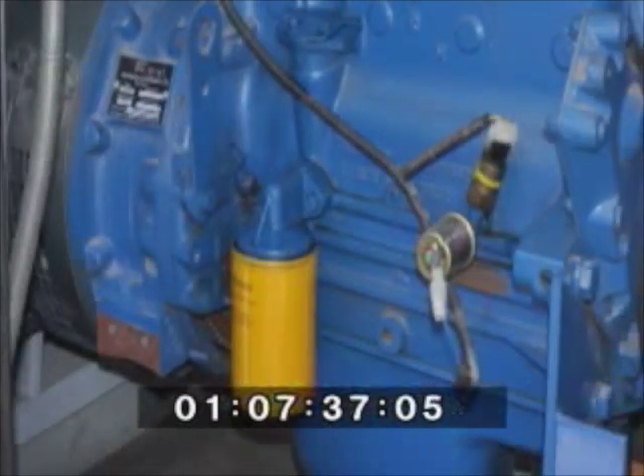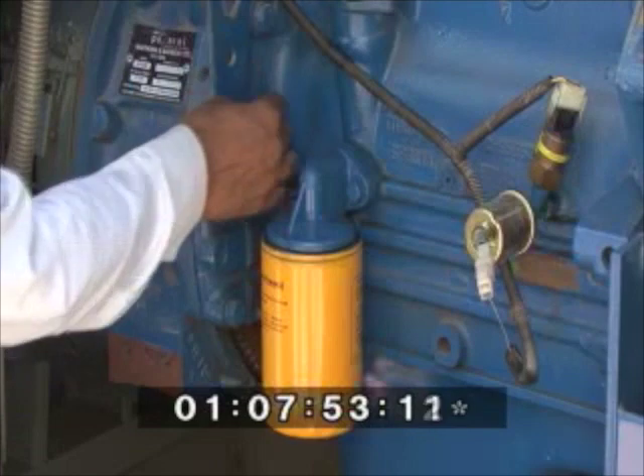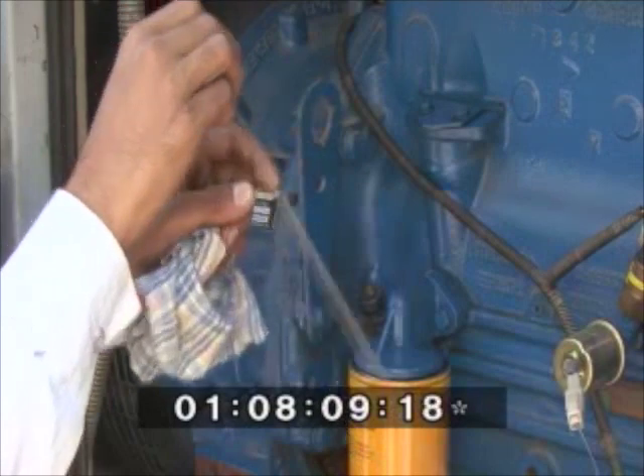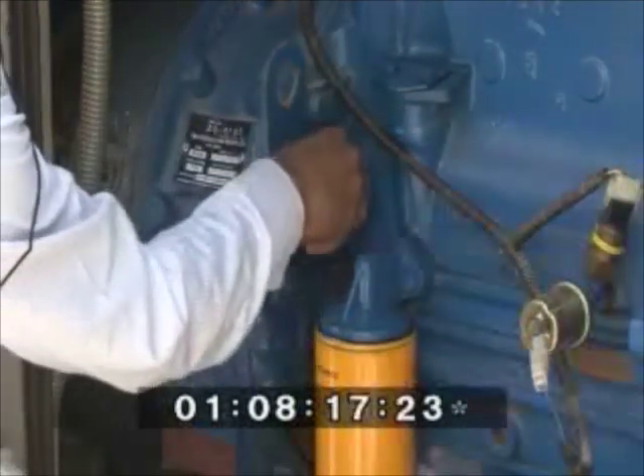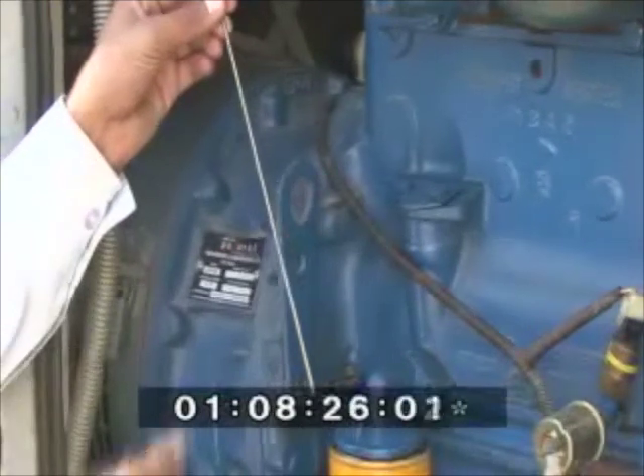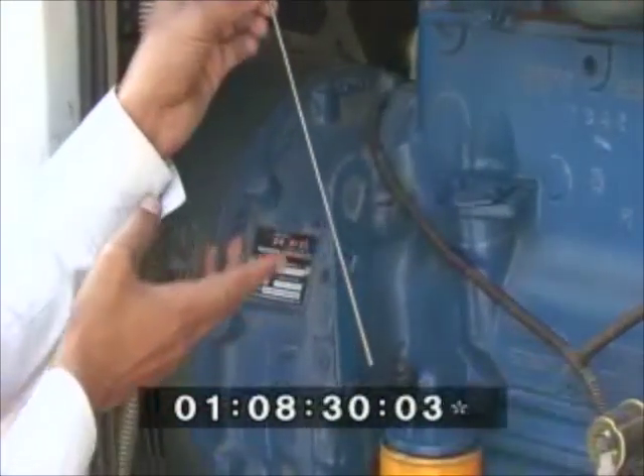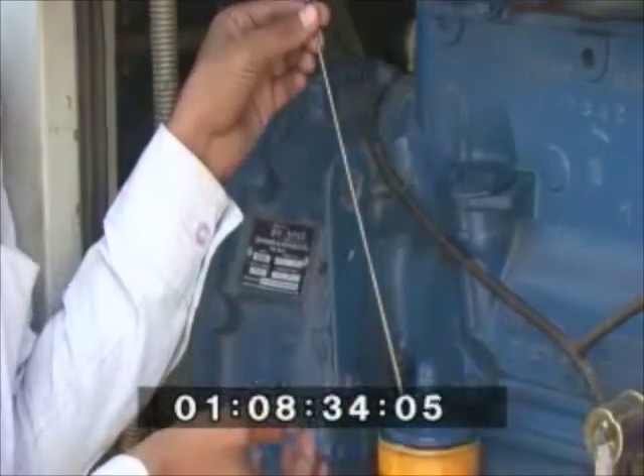Now we will do a DG lubricant oil check. We will check the lube oil level and quality in the DG set from this check. You can see the stick in the checkpoint. We will first pull out the stick and wipe it with a cloth. You can see 2 markings on the stick, one low and the other high. Now we will again immerse the stick in the DG checkpoint properly. Then we will pull it out, and now we can see the oil mark is at the high level, indicating that the lubricant oil level is proper.